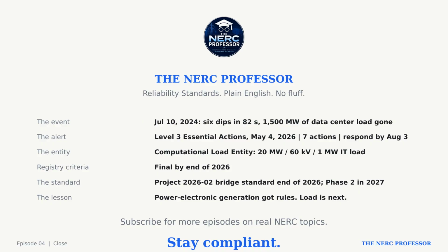A new computational load entity. 20 megawatts, 60 kilovolts, 1 megawatt of IT load. Registry criteria final by the end of 2026, and Project 2026-02, with a bridge standard expected by the end of the year. The grid spent 2 decades learning that generation built on power electronics needs rules. It is about to spend the next few years learning the same lesson about load.